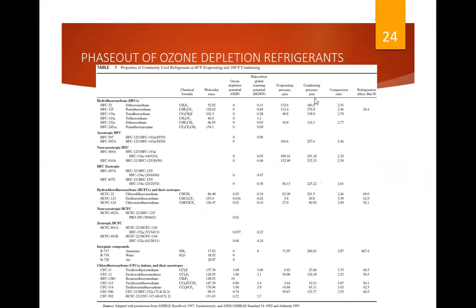Evaporating pressure, condensing pressure, compression ratio, refrigerant, and effect. So these are properties of commonly used refrigerants at 40 Fahrenheit evaporating and 100 Fahrenheit condensing. The saturation pressure is 135.6 at a temperature of 40, for refrigerant 32.